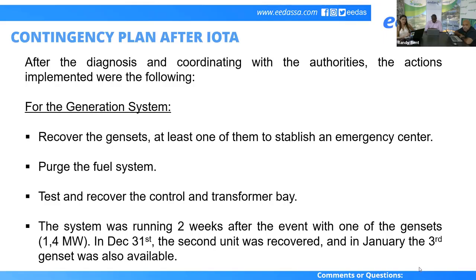Then we selected one of the tanks. There were 5 tanks at that moment. We purged the fuel system, recovered the pipe system, and installed an emergency pump station. And immediately we started to test and recover all the transformer bay and the control system. Two weeks after the event, we ran the 4th generator, the biggest one, 1.4 megawatts. And on December 31st, almost a month and 20 days after the event, we got the second unit online.